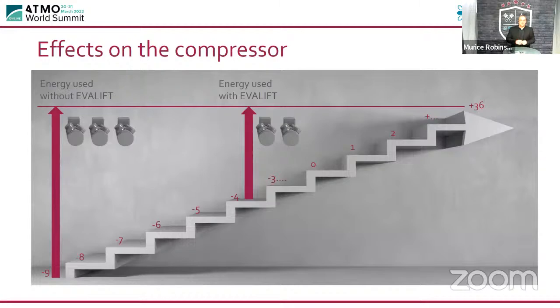So just to give you a little bit of an infographic on the effects on the compressor. As we know, if you have a suction temperature at -9, the compressors basically have to get that gas all the way up to 36 degrees on the other side, so that it can go through the whole cycle again. So from -9 all the way up to 36, you've got a very high delta that you have to make sure the compressors are pumping. So you're going to need, let's say, 3 compressors. With EVALIFT, or with just increasing your suction temperature from -9 to -4, you might only need 2 compressors. So it actually benefits you, and you can see the benefit even on a desktop simulation.